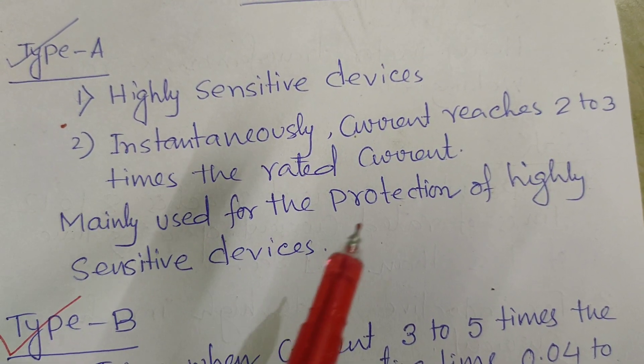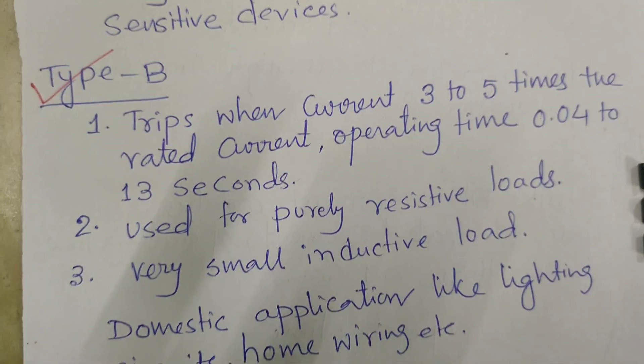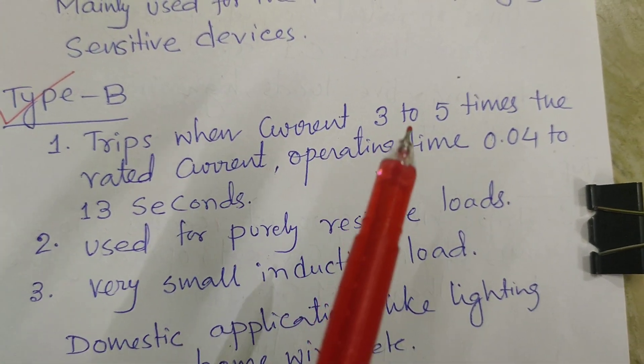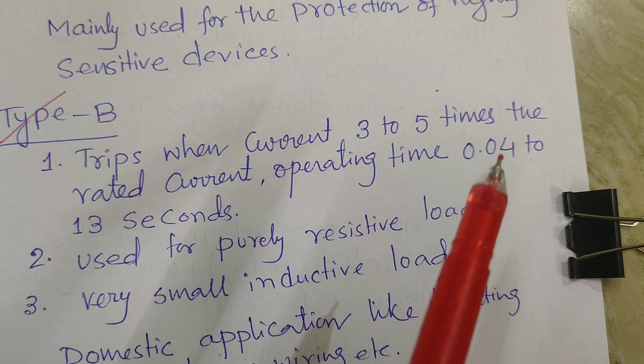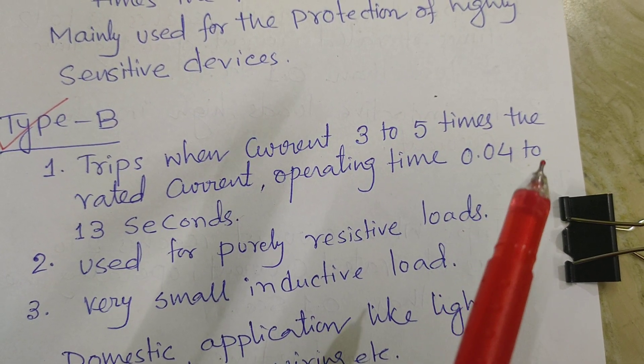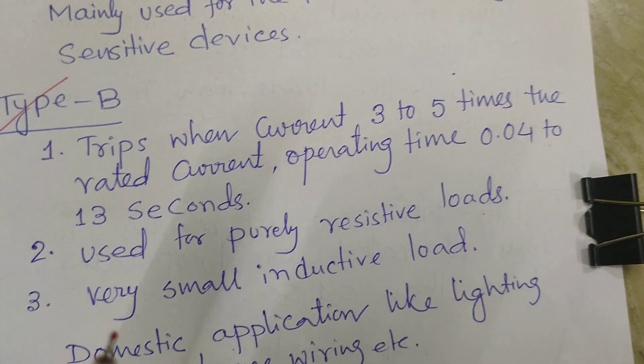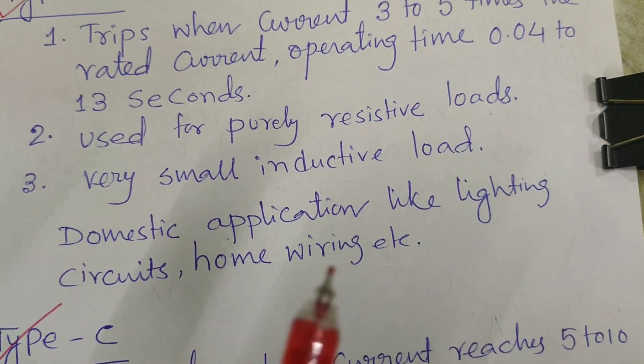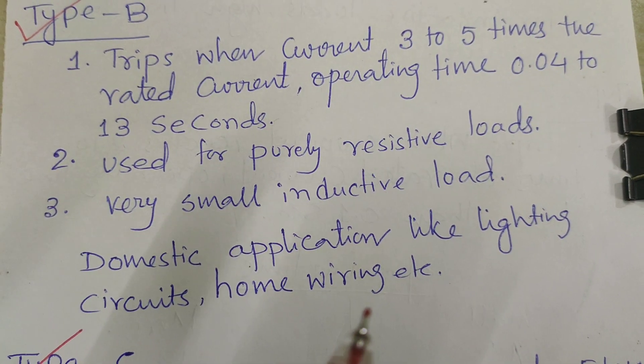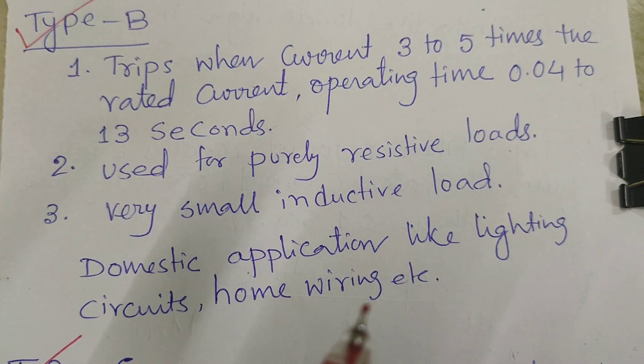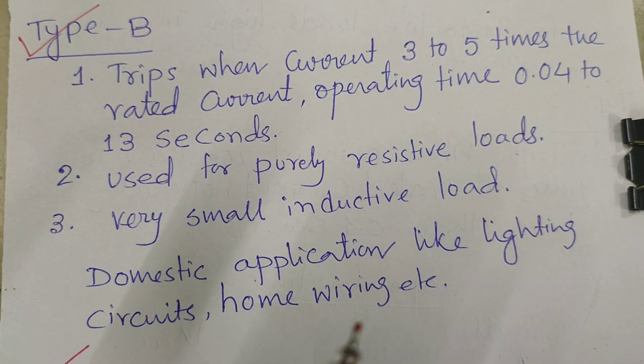B-type trips when current reaches 3 to 5 times the rated current. Operating time 0.04 to 13 seconds. Used for purely resistive loads, very small inductive loads, domestic application like lighting circuits, home wiring, etc. We are using the B-type MCBs. And in the starting of the video, I showed you the B-type MCB. So, B-type MCB is used for the domestic purpose.